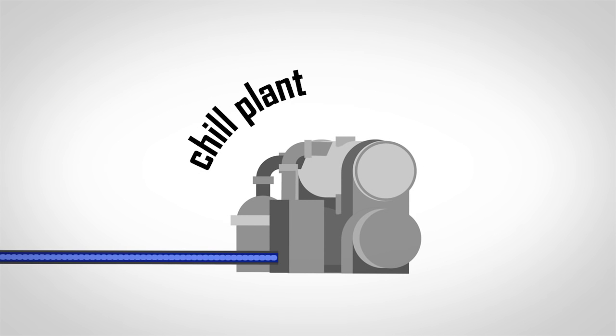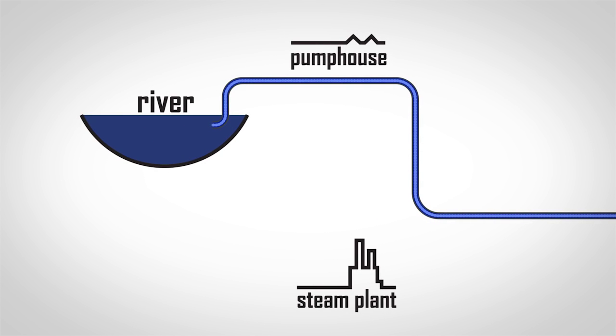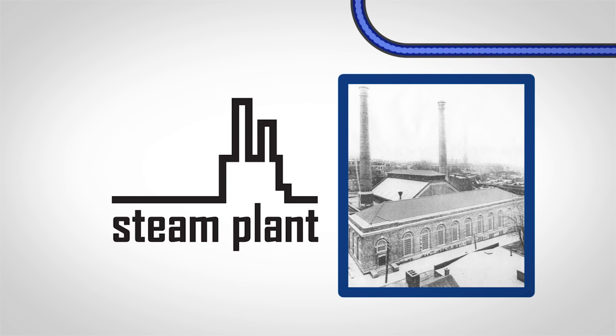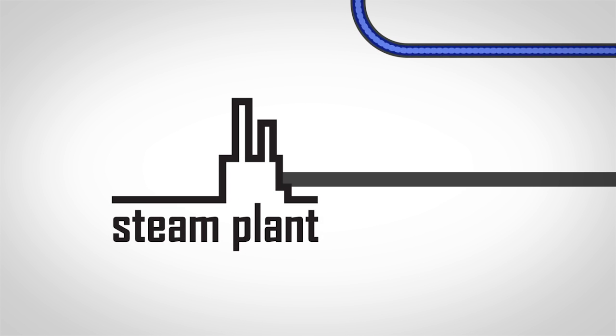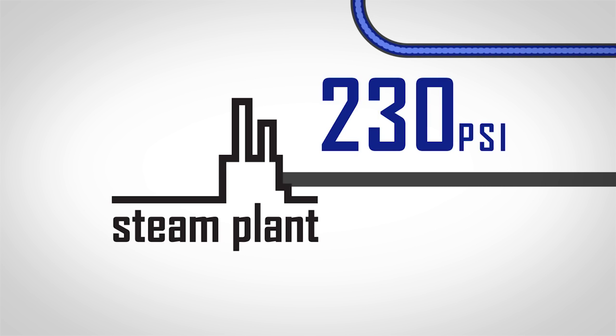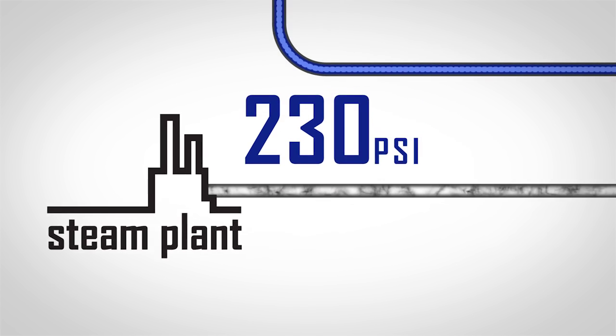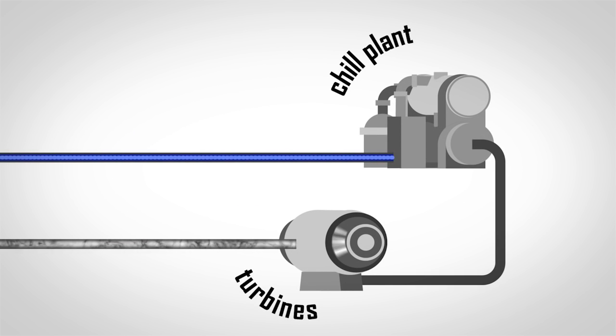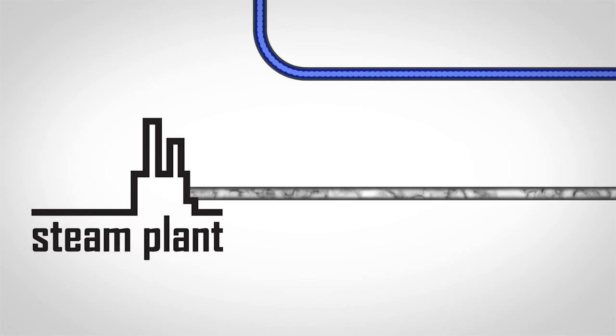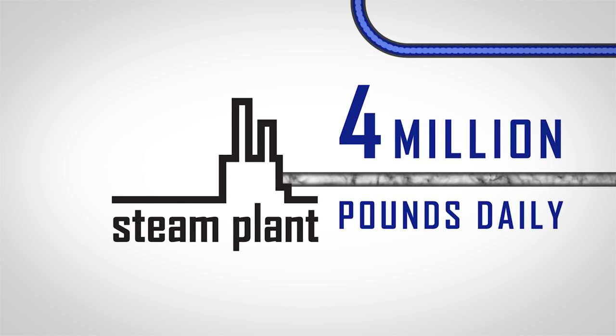However, that's only one half of the cooling equation. The other half resides several city blocks away at the Sheridan Steam Plant. Originally named the Capital Powerhouse back in 1911, the Sheridan plant delivers steam at a steady pressure of 230 pounds per square inch to power the chill plant's turbine engines. On some days, upwards of 4 million pounds of steam is generated at this location.